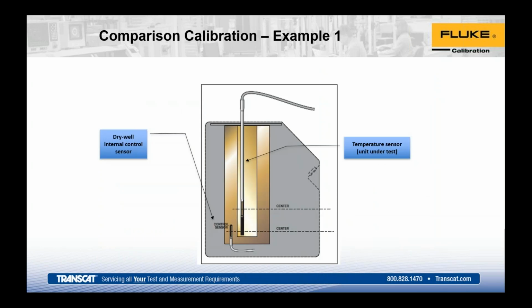In this first example, it's a calibration example of, say, an industrial sensor that you're calibrating directly in a dry well. So in here, you're going to be calibrating directly to the control sensor of the dry well. Depending on the dry well type and range, dry wells can go from a half a degree or better. Sometimes you get down to 0.2, 0.1 on the display accuracy. We'll touch on this further, but depending on what you're testing, most folks will try to hold to a 4-to-1 type uncertainty. Most processes require you to be some level better, and in the industry, 4 times better than whatever you're calibrating is very common.